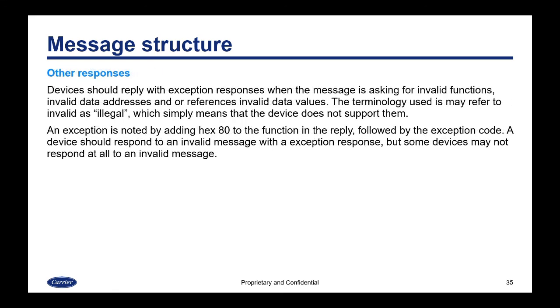Devices should reply with exception responses when the message is asking for invalid functions, invalid data addresses, or invalid data values. The terminology used may refer to invalid as 'illegal,' which simply means the device does not support them. An exception is noted by adding hex 80 to the function in the reply, followed by the exception code. A device should respond to an invalid message with an exception response, although some devices may not respond at all. The good thing about an exception response is that you know the device is connected correctly, since you are receiving a valid message in return — it is just telling you that the data or address you asked for is invalid.